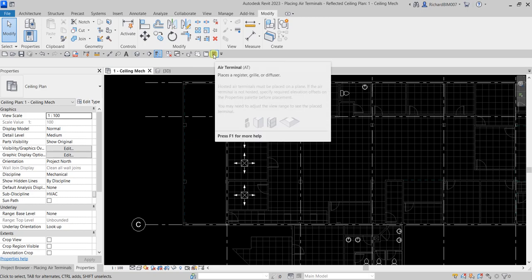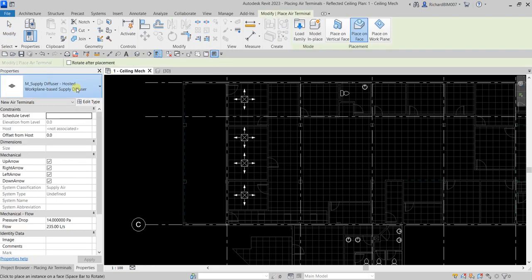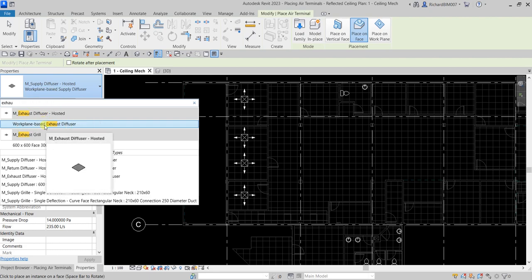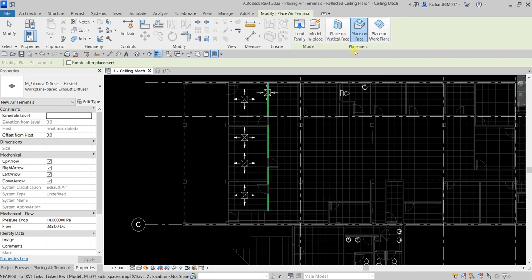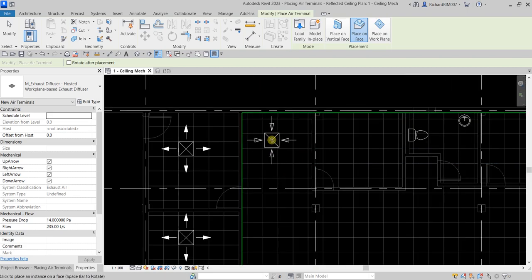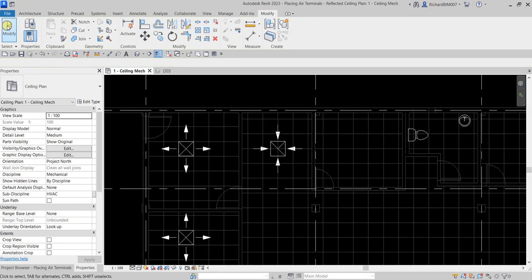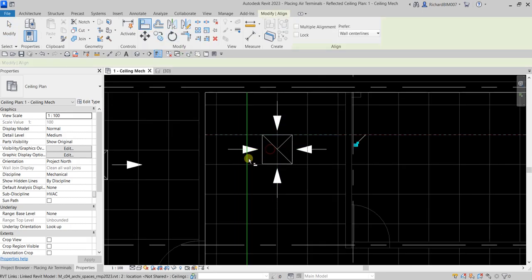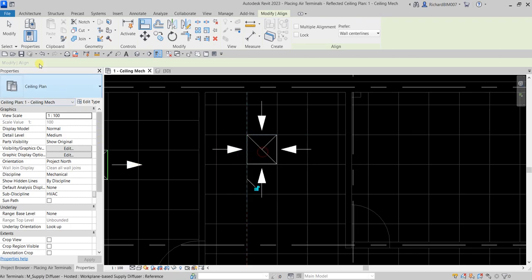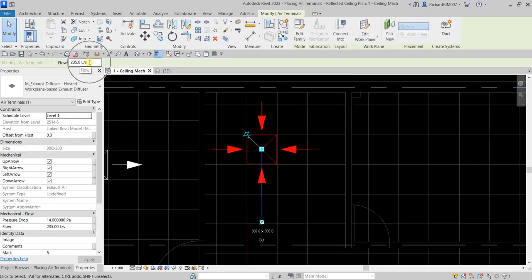From the Quick Access Toolbar, click the air terminal tool. Search for 'exhaust' and select Exhaust Diffuser Hosted. Make sure Place on Face is selected, place it on the ceiling, then select Modify. Use the Align tool to position it, then click the terminal and change the flow rate to 150 liters per second.